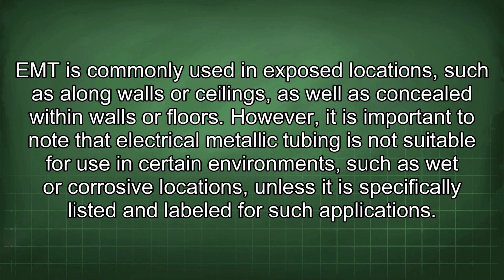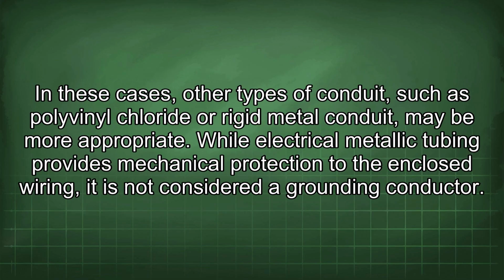EMT is commonly used in exposed locations, such as along walls or ceilings, as well as concealed within walls or floors. However, it is important to note that electrical metallic tubing is not suitable for use in certain environments, such as wet or corrosive locations, unless it is specifically listed and labeled for such applications. In these cases, other types of conduit, such as polyvinyl chloride or rigid metal conduit, may be more appropriate.